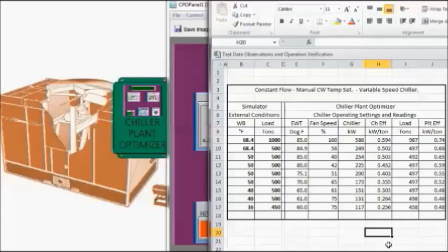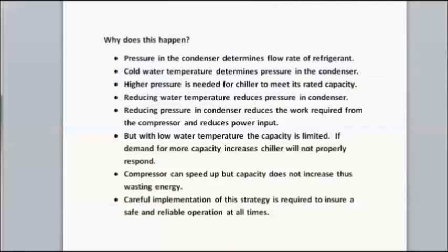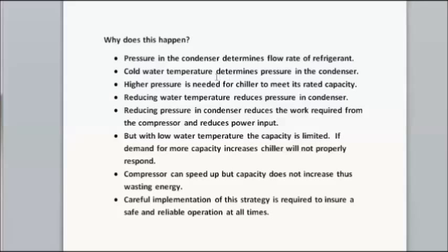Here is a summary of how this condenser water reset works. We're dealing with the refrigerant pressure in the condenser because that determines the flow rate of refrigerant. The cold water temperature determines the pressure of the refrigerant in the condenser. You need a higher pressure for the chiller to meet its rated capacity with a required flow rate of refrigerant.